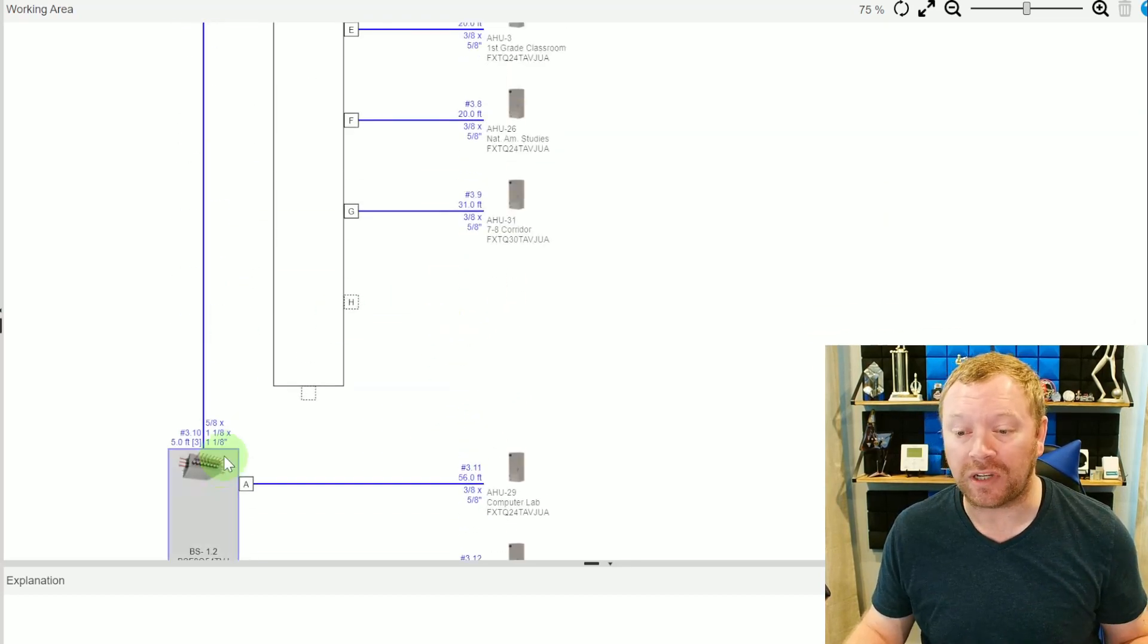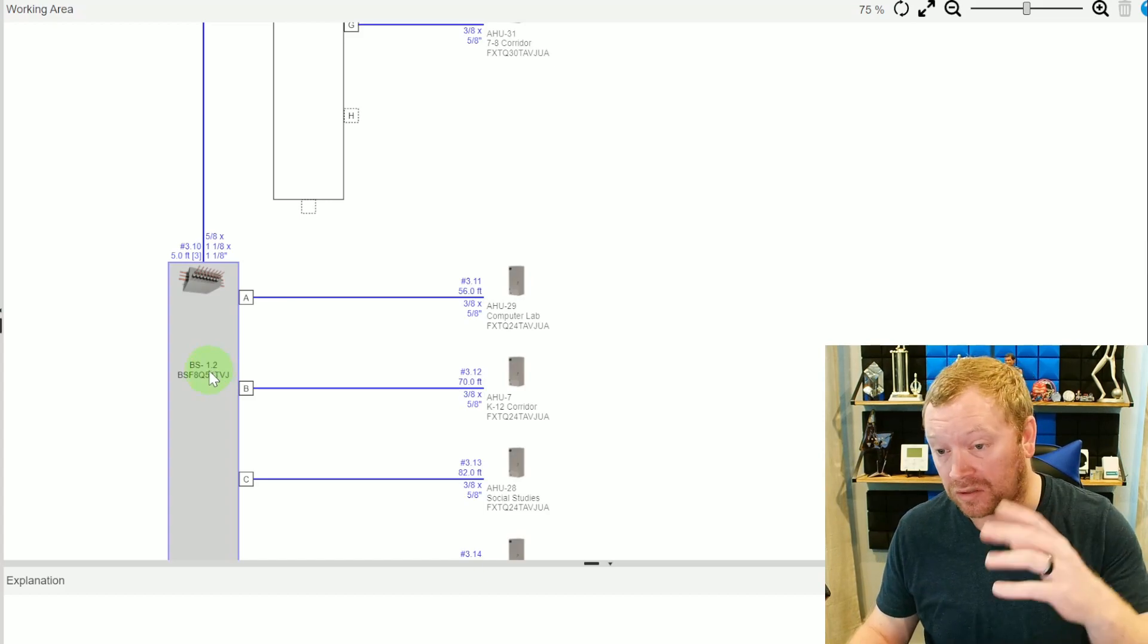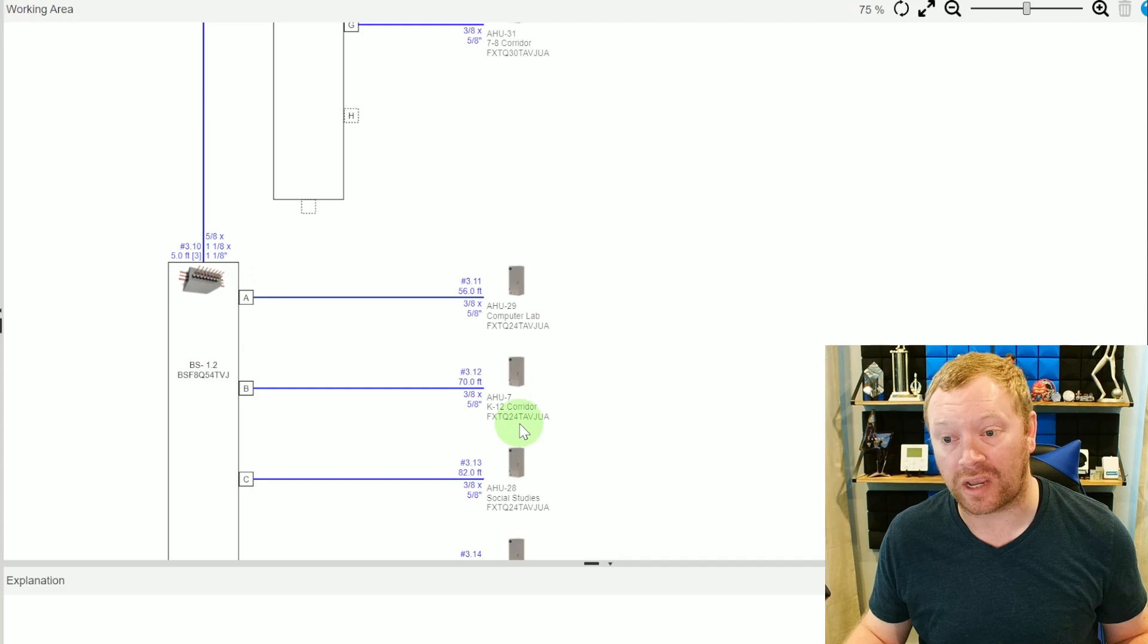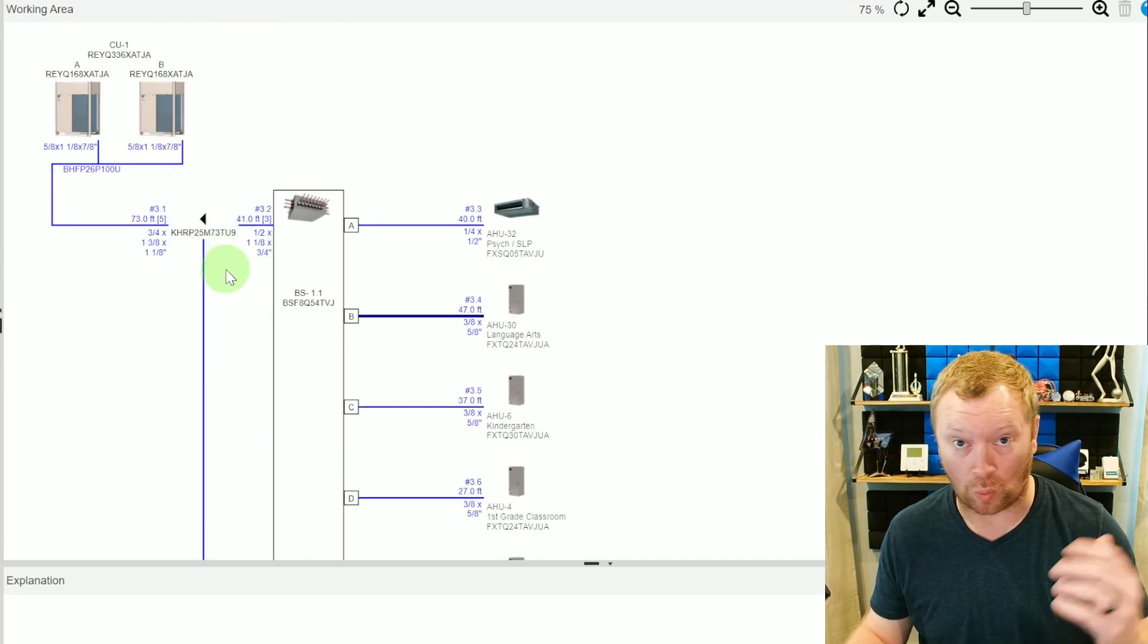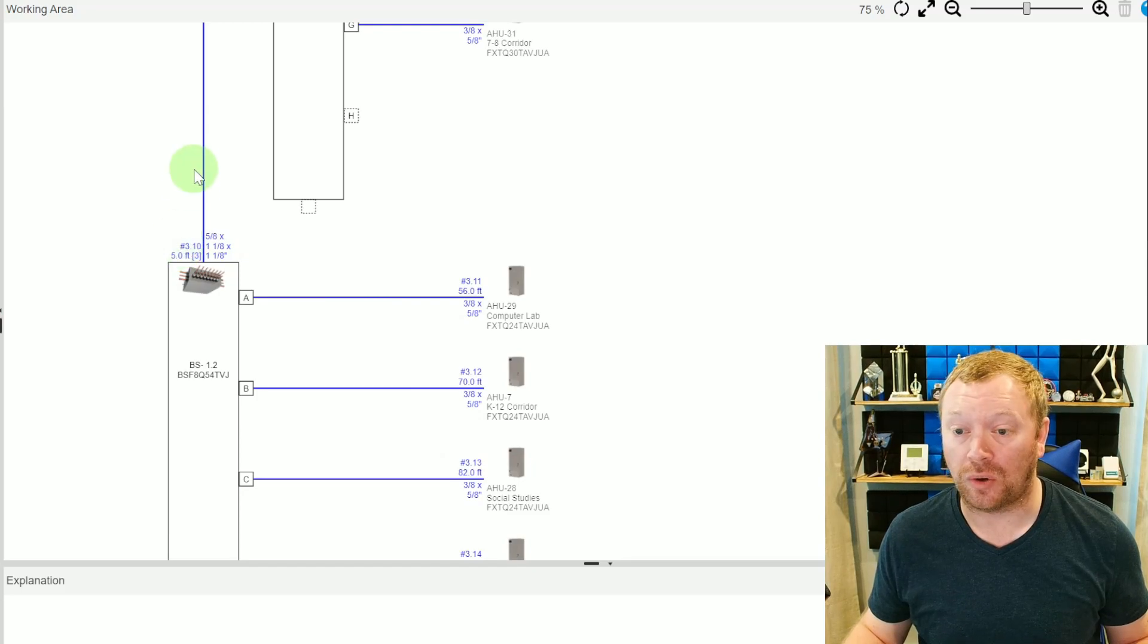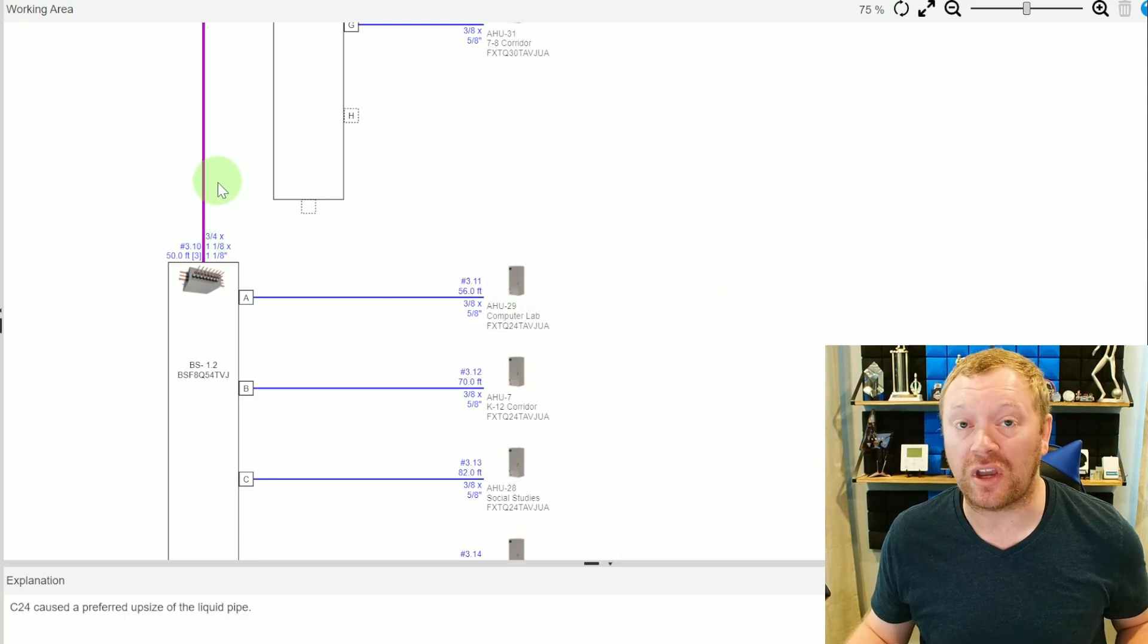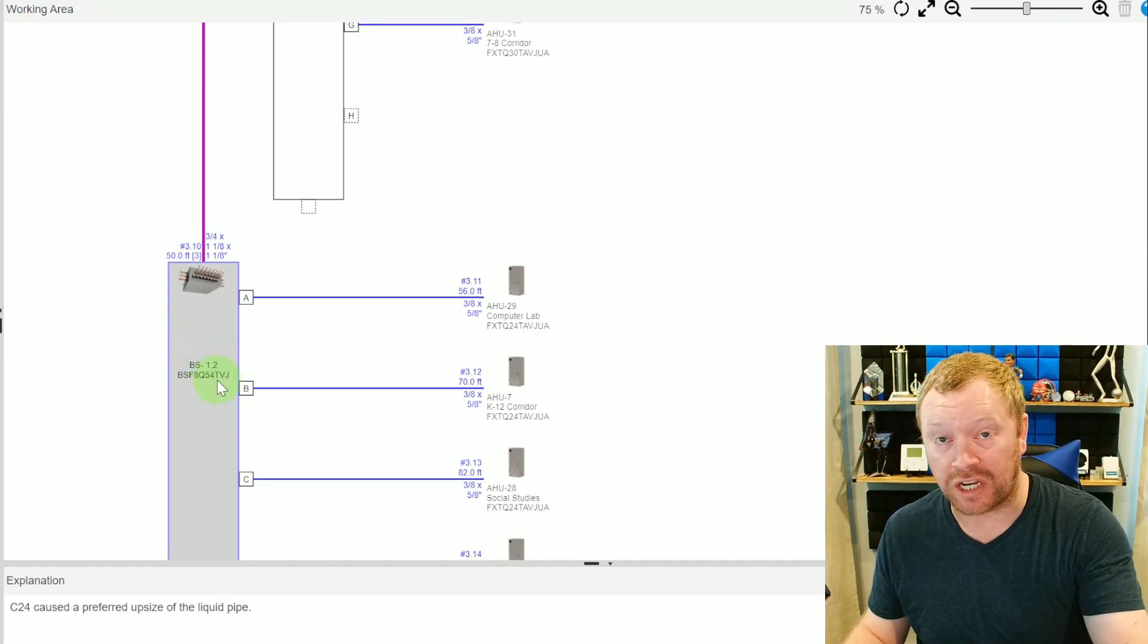I digress. That's not necessarily part of today's video. But sometimes these indoor units will actually get moved to the other branch box. And sometimes the labels of these branch boxes are going to change. BS1.2 may have been BS1.1 on the plans. And then the label somehow got changed in the field because they relocated these boxes. Whereas five eighths, one and one eighths, one and one eighths, this box connected to these air handlers originally may have been drawn in at the 41 feet. And then they switched a bunch of stuff around. Where I'm going with this is I've had many cases happen, one this week, that really irked me. And that's why I'm bringing this up and talking about it today where BS1.1 was down here connected to these units and the length was much longer than five feet.